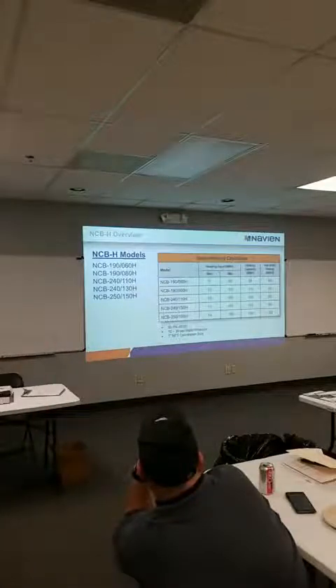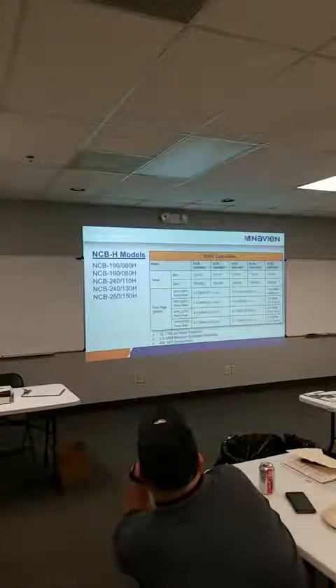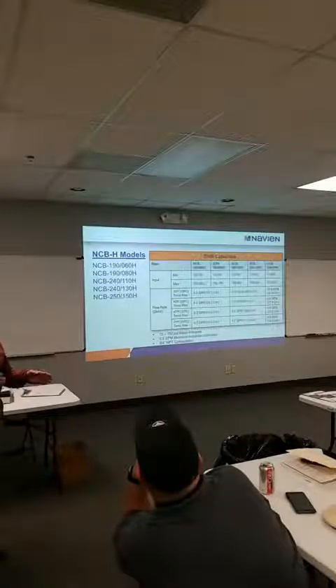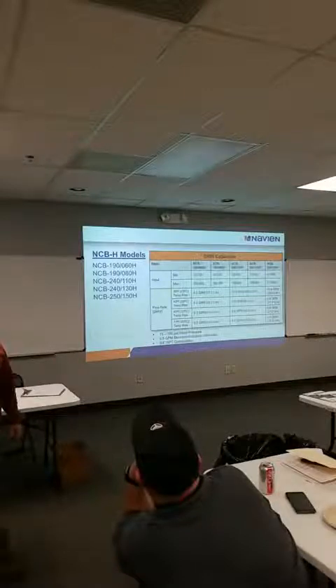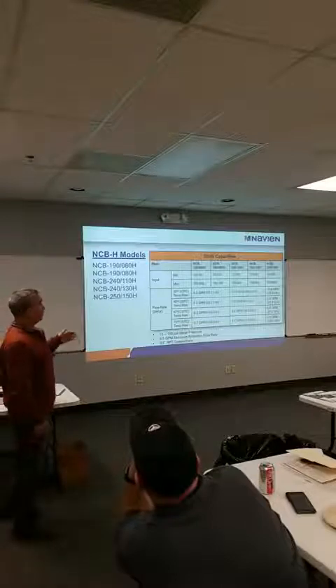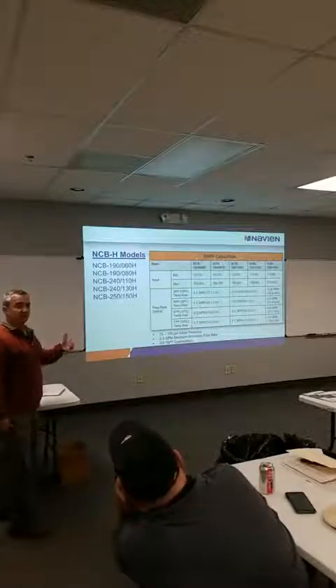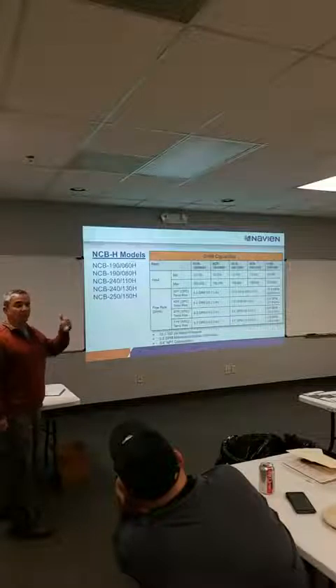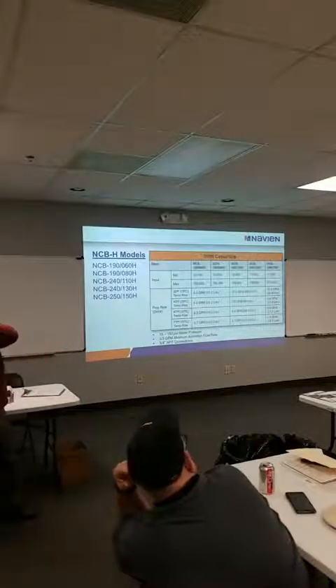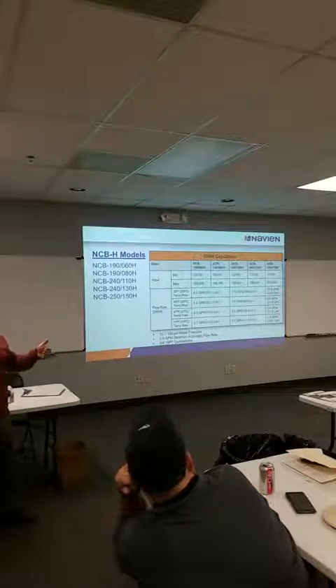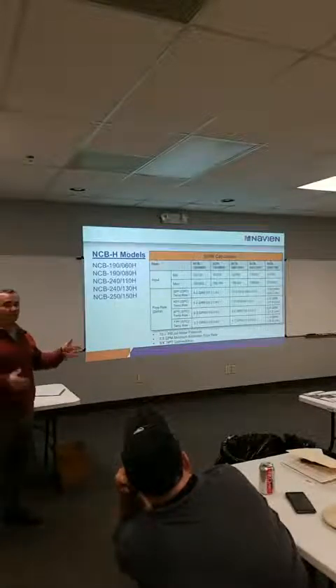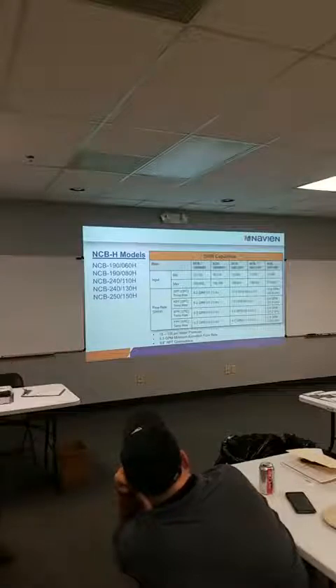What do you see the temperature rise at on the domestic? It's modulated, so our charts go from like 35 to 90. So the colder the domestic inlet is, the hotter it's going to fire. Yeah, so 55 in, you can hit 145 at full fire. The max domestic temp is 140 on these units, but you can get up to 194 on the heating side, because the NCB is really a residential model. The NFC combi, we do residential or commercial, so it's set up a little different.